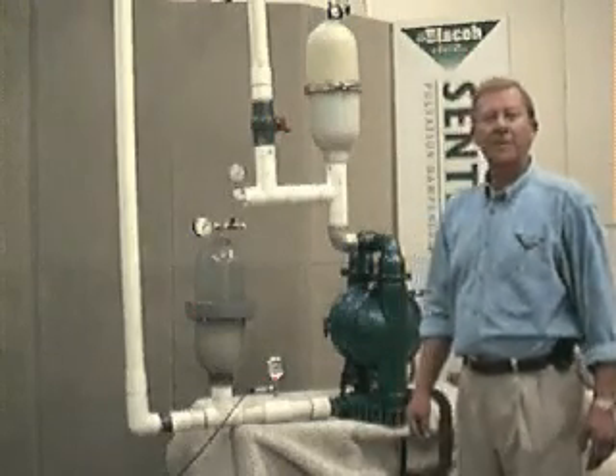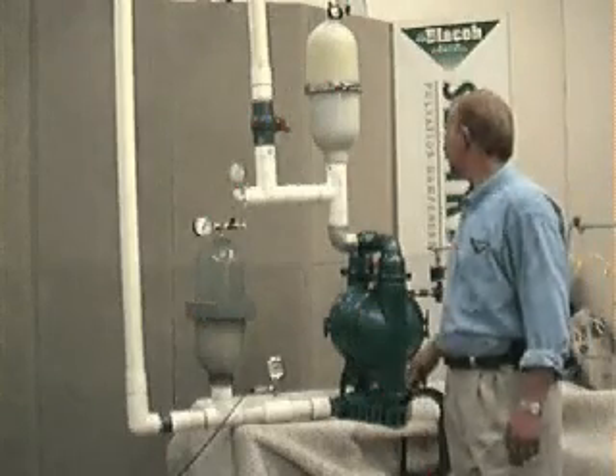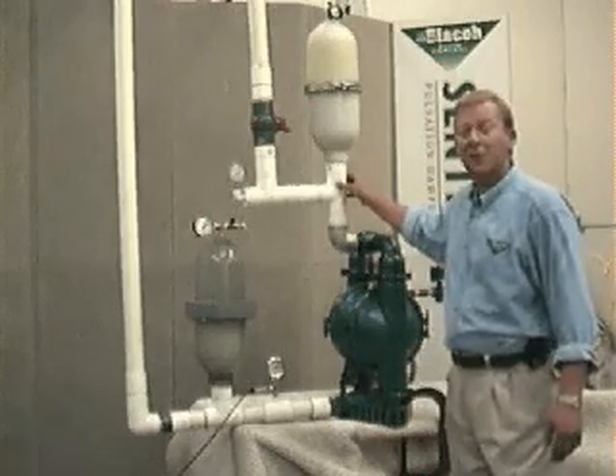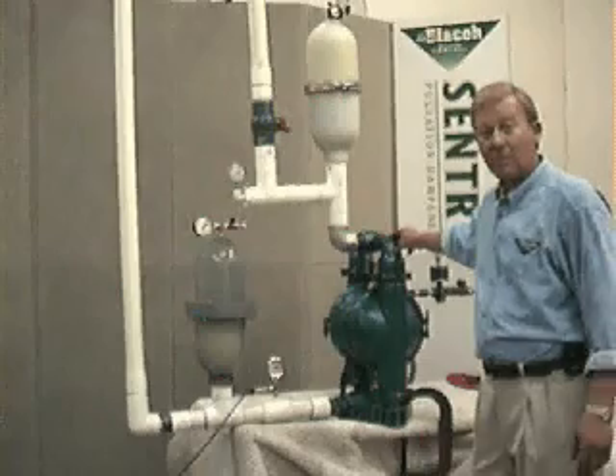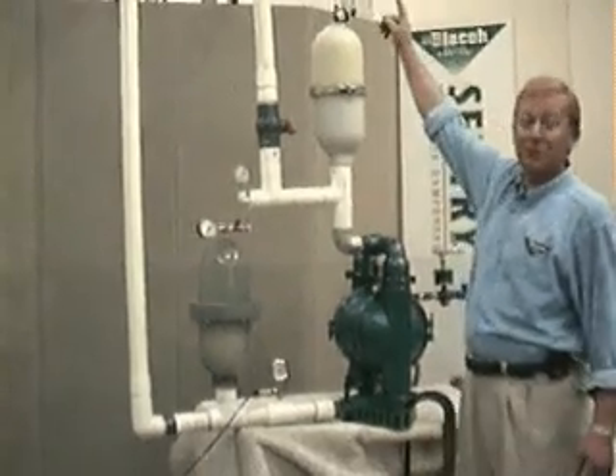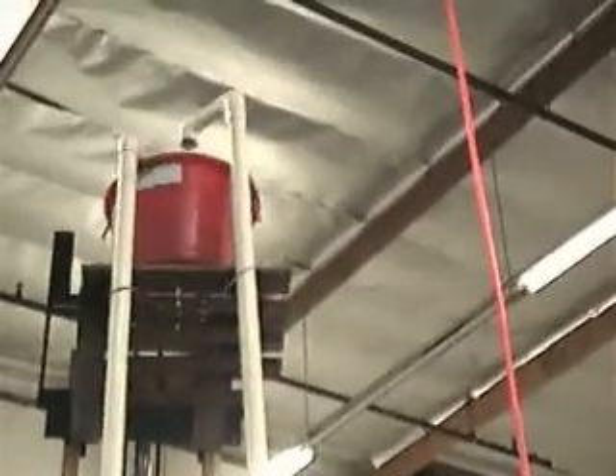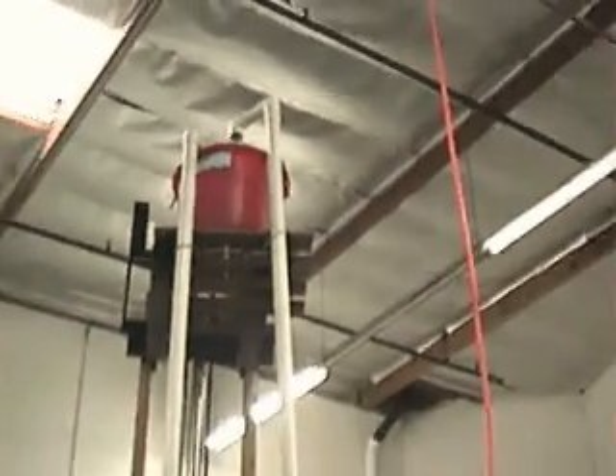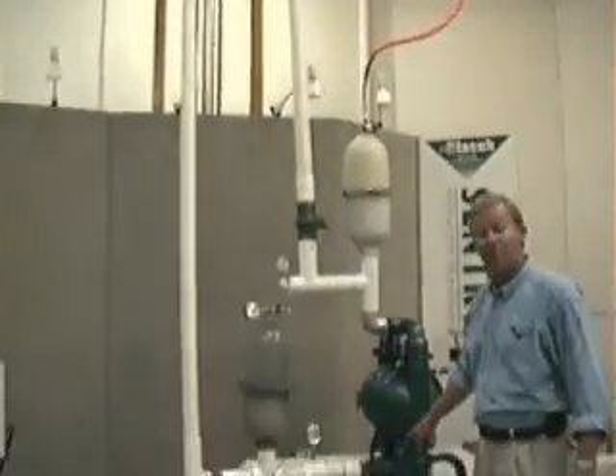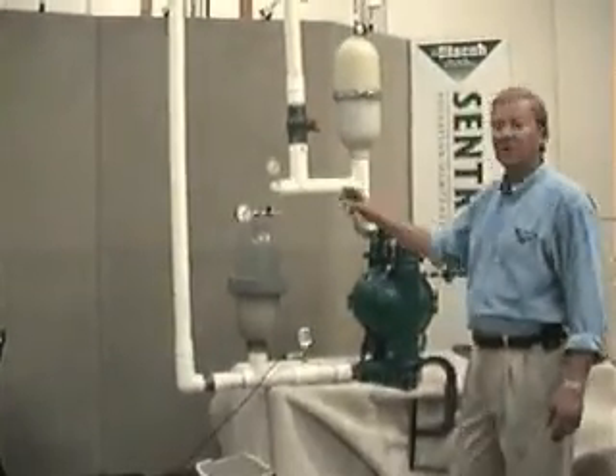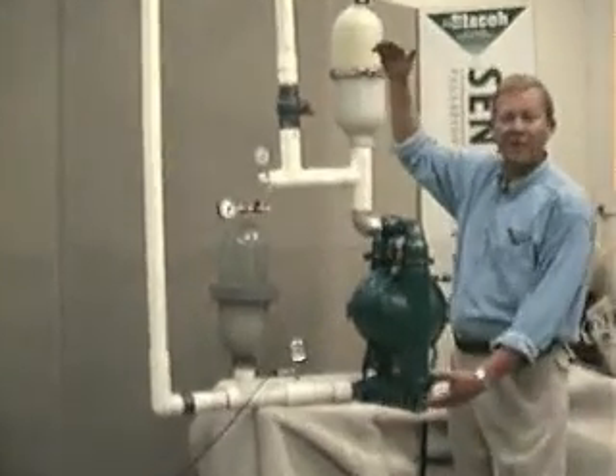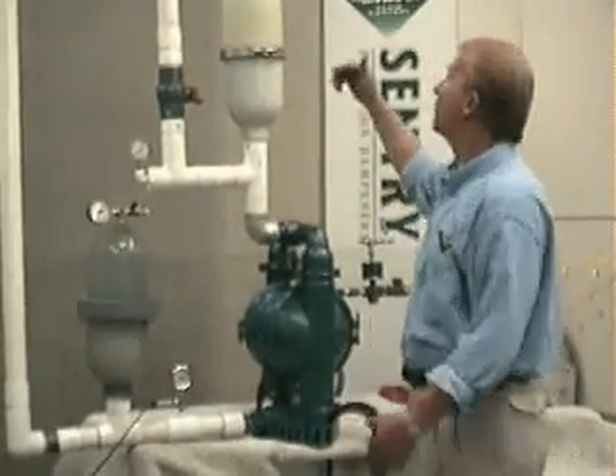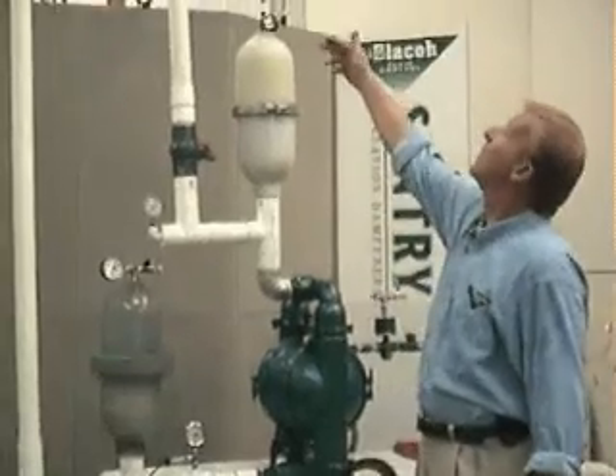Hello again. This test stand is set up to demonstrate the effects of pulsation from a reciprocating pump with a high discharge and with a high inlet pressure coming into the pump. This simulates a tall tank feeding the inlet to the pump, and we've accomplished this by using a forklift with a tub of water approximately 12 feet in the air.